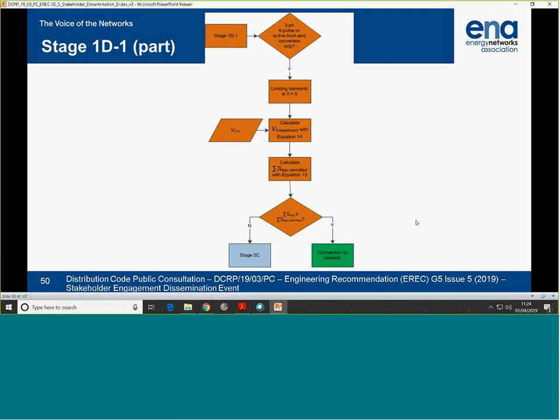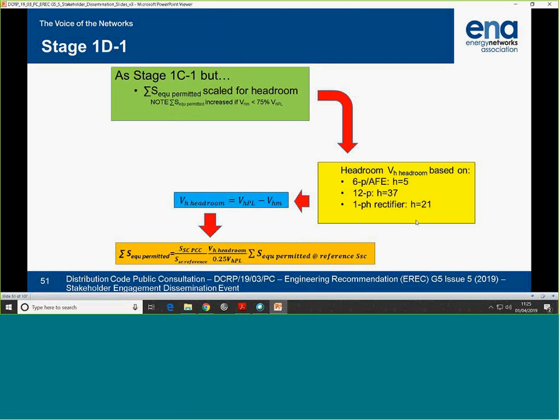So the DNO is then measuring the background distortion at the point of coupling, or as much as they can get. Then we have a calculation of the headroom, so what's left for headroom earlier, and calculating a permitted rating of equipment you can connect. So if we go on to the next slide.